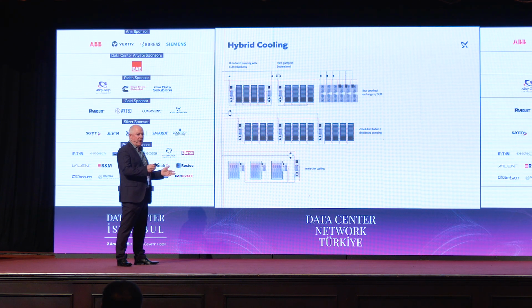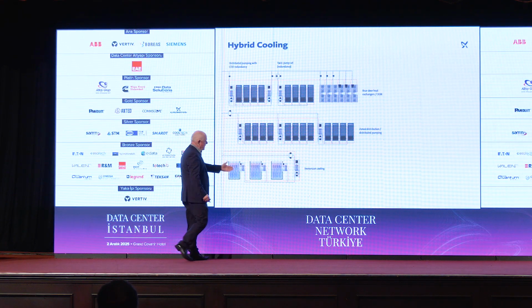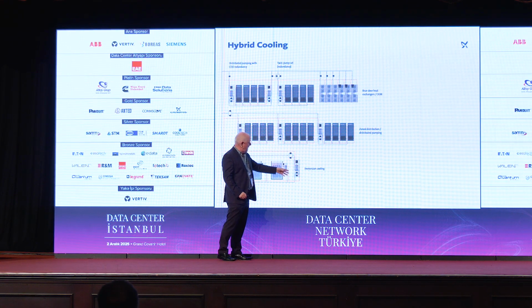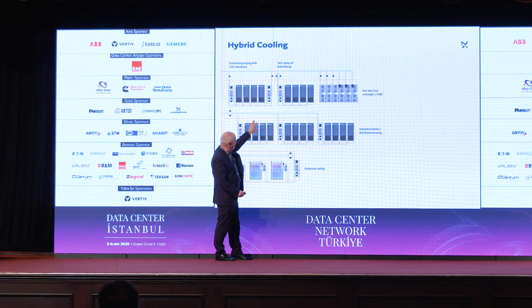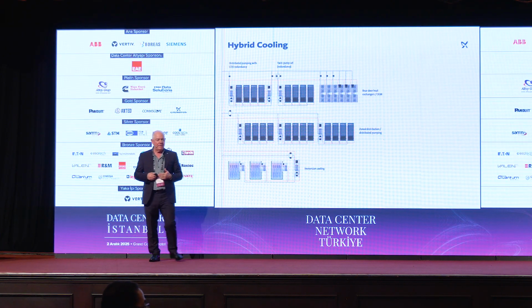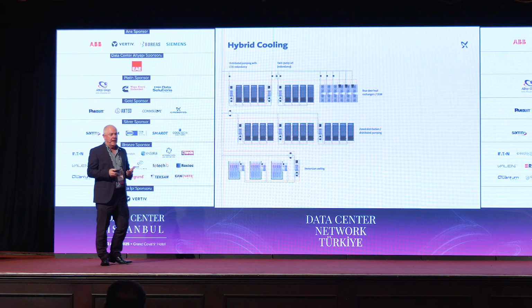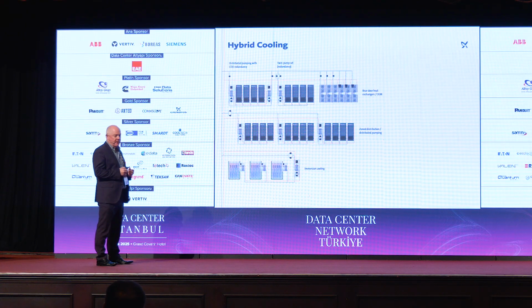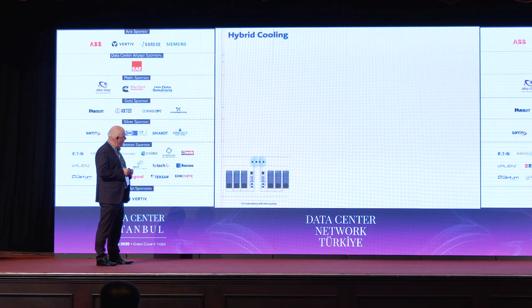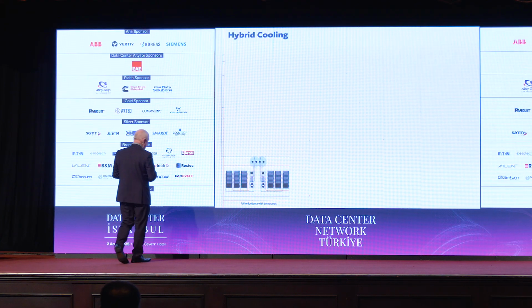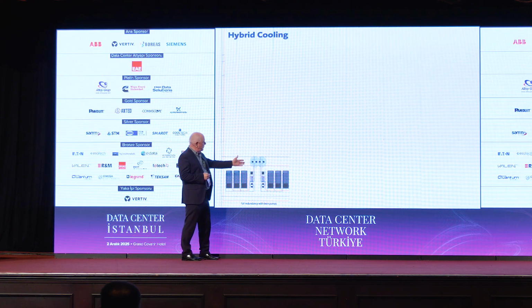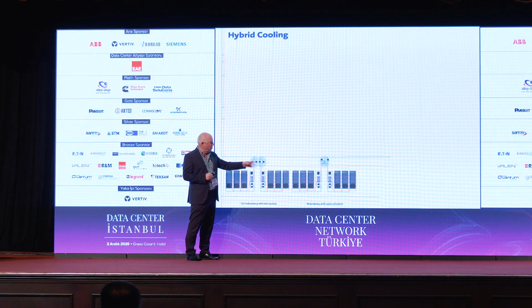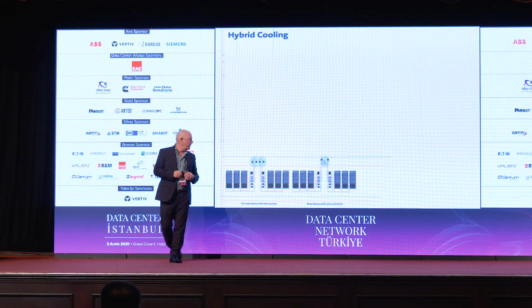And if we look at different loads, as I mentioned, we can use this with hybrid cooling systems where we have a mixture of air and water or liquid cooling. We have different applications down here on different levels, and we have a pump or 2 pumps as a standby, which is meeting the load on each of these applications. We've got different ways of doing redundancy. We can see we've looked at twin pumps here, or we've got a valve arrangement here.